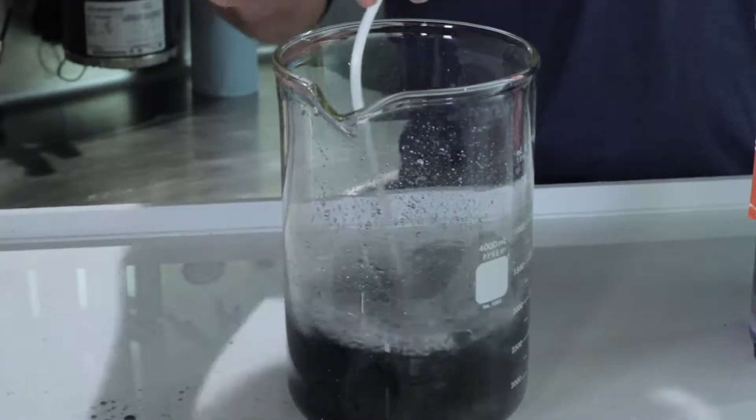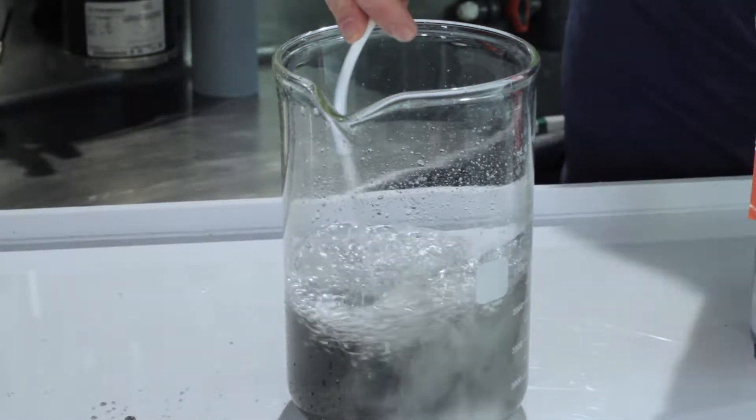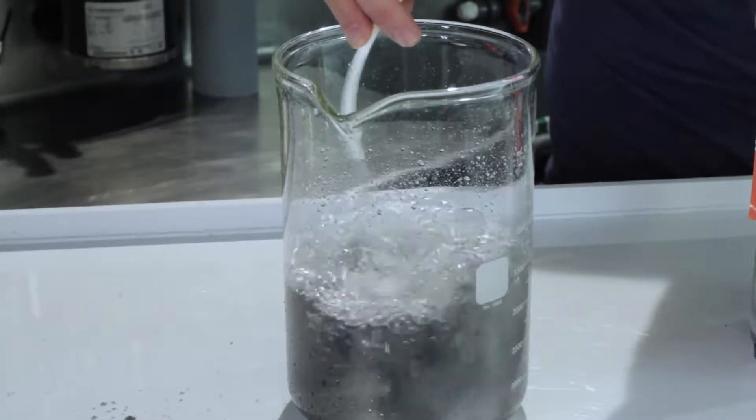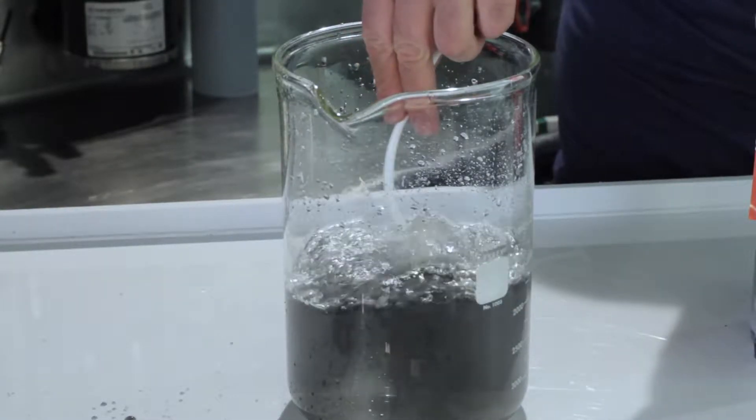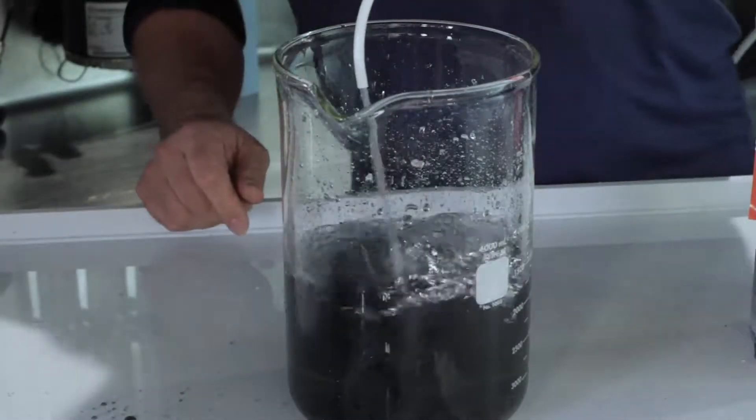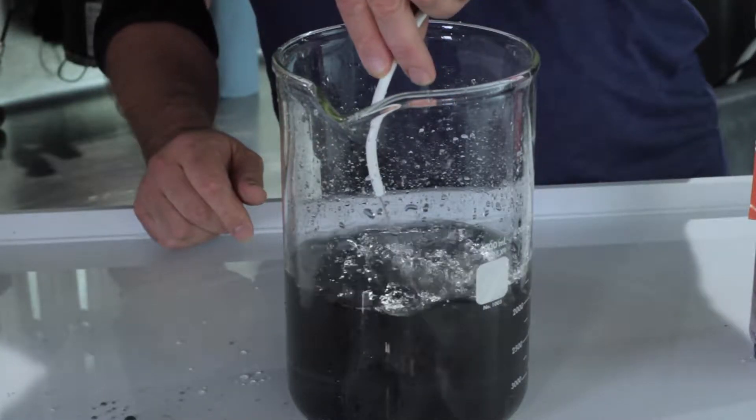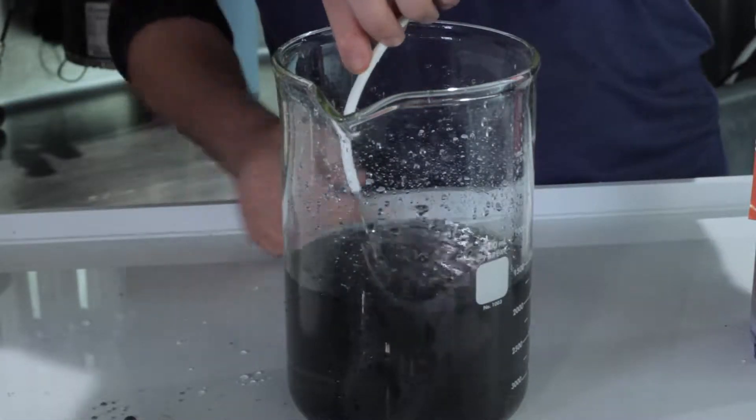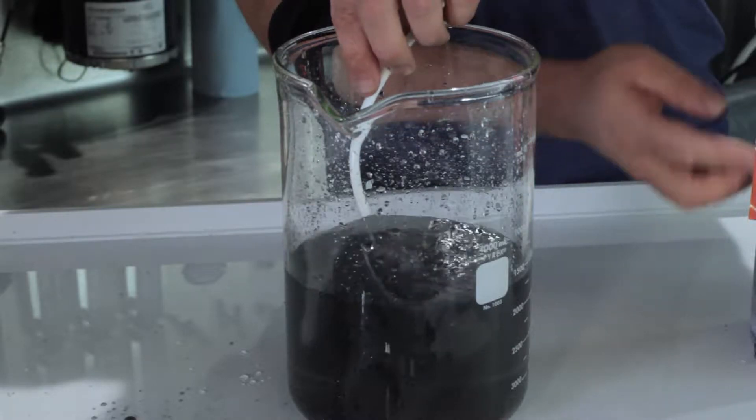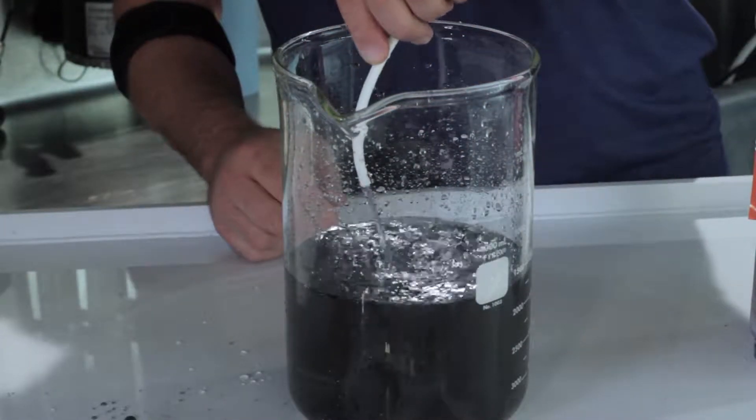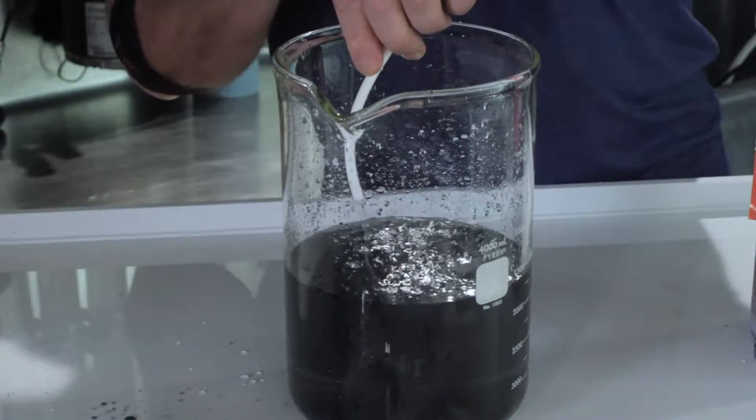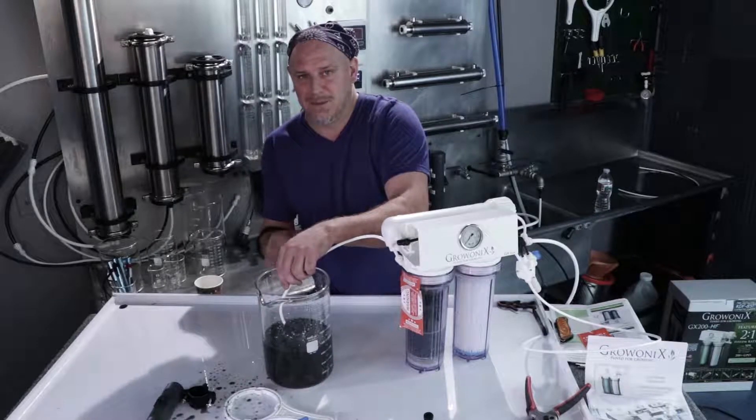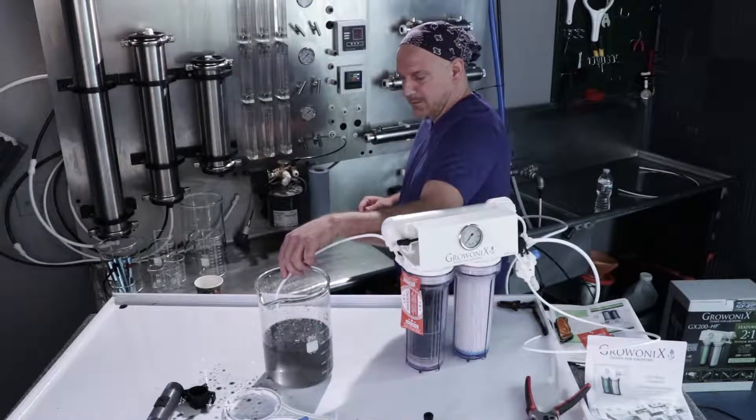You'll notice there's a lot of air bubbles. I'm going to turn the water pressure down a little. You're going to notice there's a lot of air pockets coming out with the carbon dust. That's because the carbon has a lot of air pockets in it. You want to run this until the water comes out as a smooth stream and there's no air pockets bubbling out.